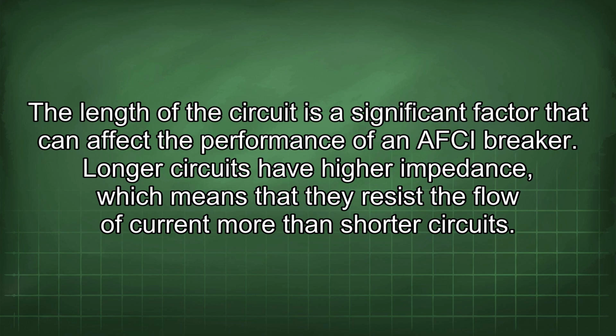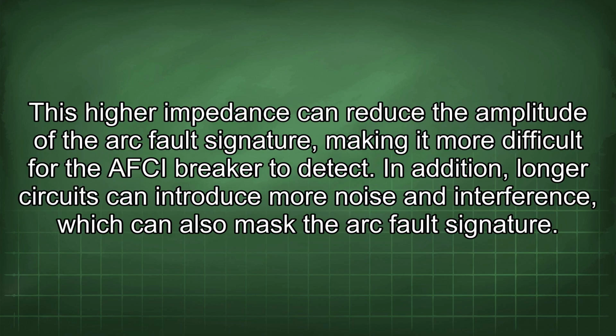Longer circuits have higher impedance, which means that they resist the flow of current more than shorter circuits. This higher impedance can reduce the amplitude of the arc fault signature, making it more difficult for the AFCI breaker to detect. In addition, longer circuits can introduce more noise and interference, which can also mask the arc fault signature.